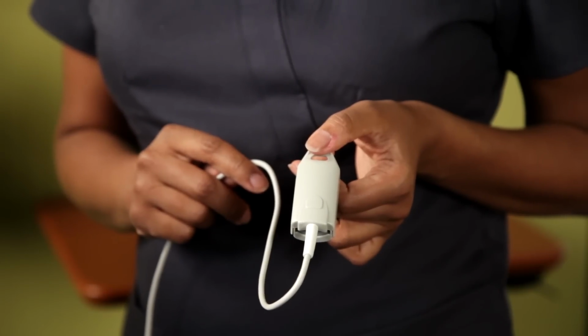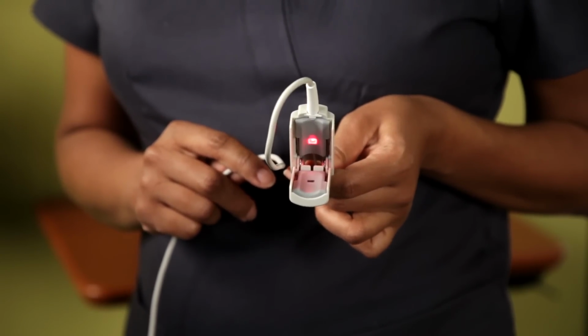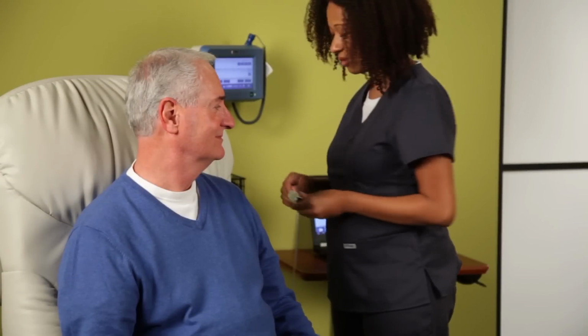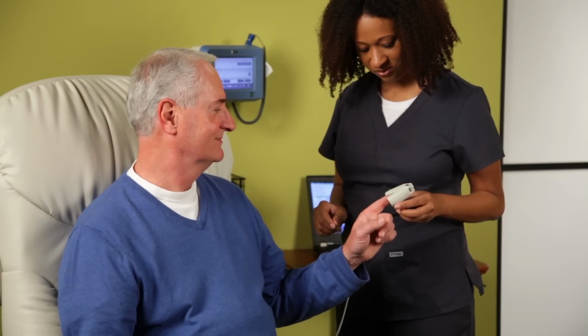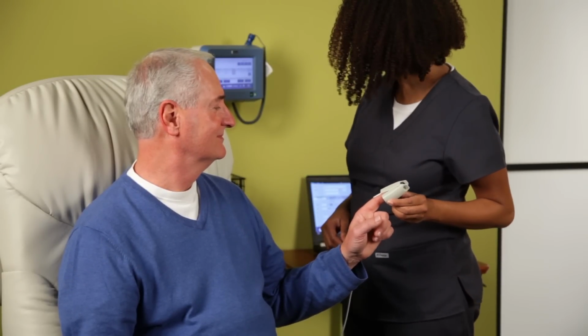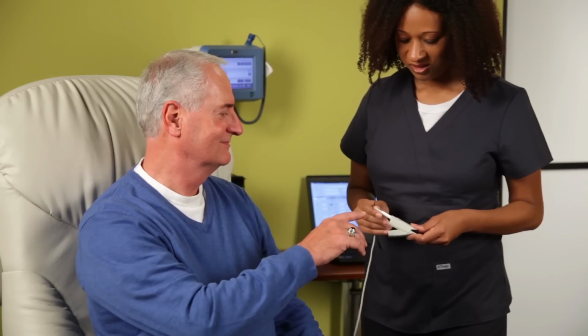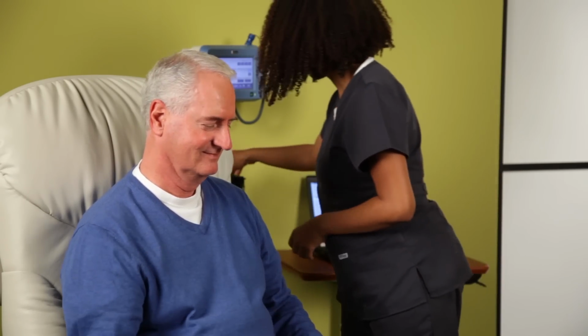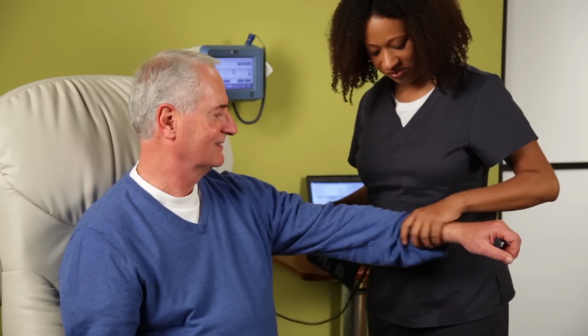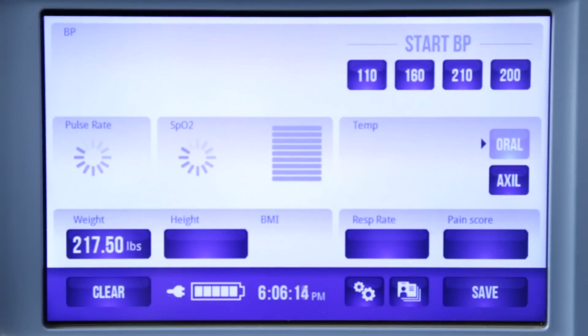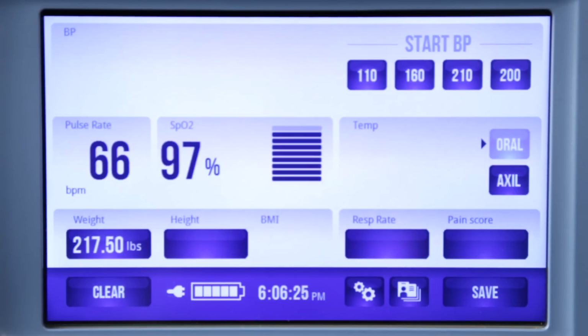To perform an SpO2 measurement, place the sensor with the LED light positioned at the fingernail. Insert the patient's finger, using the left or right index finger, completely into the sensor. If a blood pressure measurement is occurring simultaneously, place the finger clip sensor on the limb opposite the one with the blood pressure cuff. When the sensor is attached to a patient's finger, an audible tone will sound and the in progress wheel will appear. Once the measurement is done, another audible tone will sound and the SpO2 value will appear. If the sensor remains on the patient, the pulse rate bar on the screen will become active.